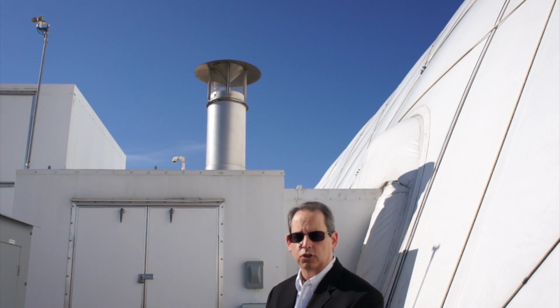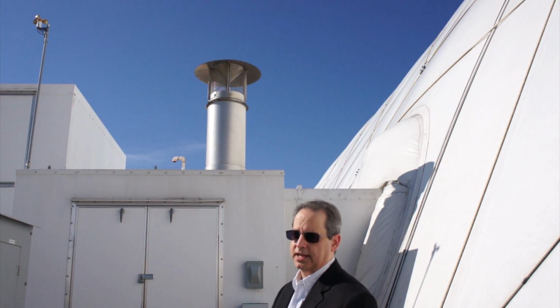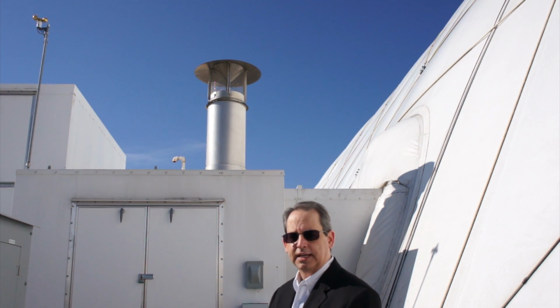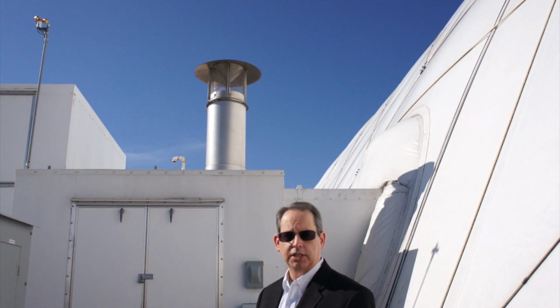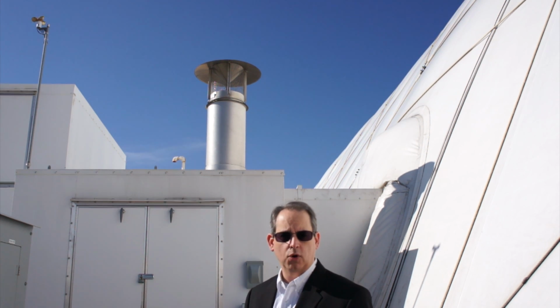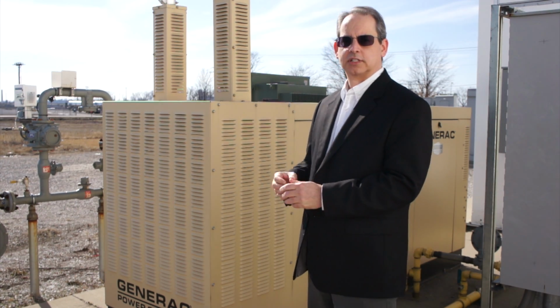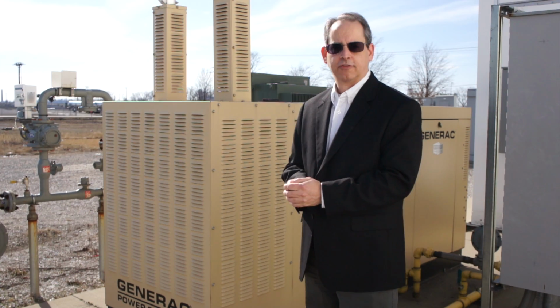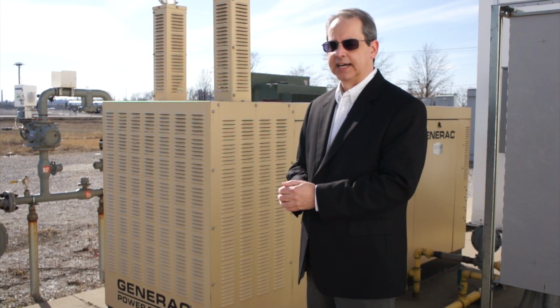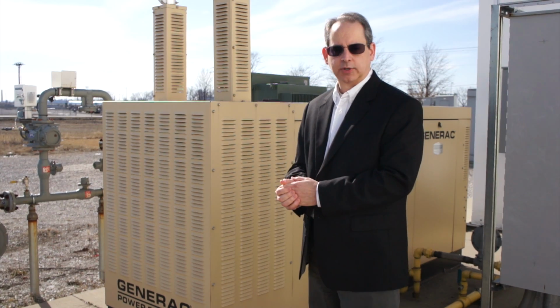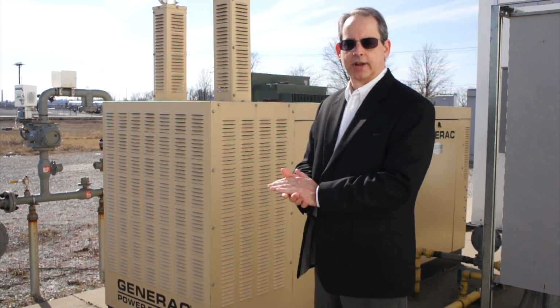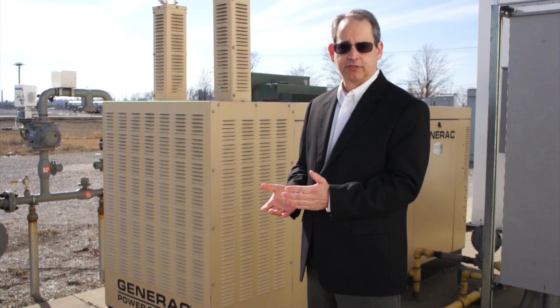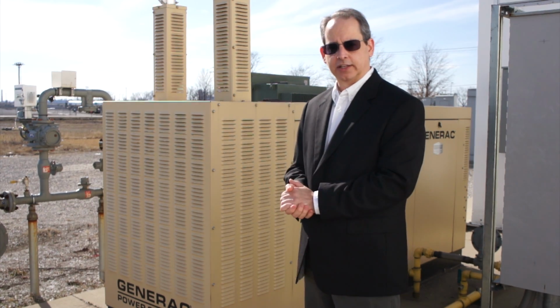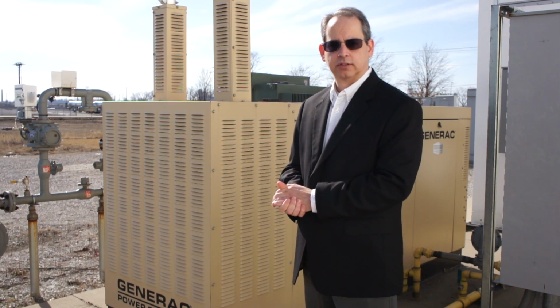And then optional equipment, optional items on the unit include a wind sensor like we have on this unit, in addition to a snow sensor. Those two items can be used to put the unit into a bad weather mode for automatic building control in case of inclement weather. Arizon Structures uniquely uses standby generators as our backup power source for the backup auxiliary pressurization system. In addition, they can be easily upgraded like we did on this project with an upsized generator to not only back up the auxiliary inflation system, but to back up the entire air handling system, including the primary inflation, the heat, and the controls.